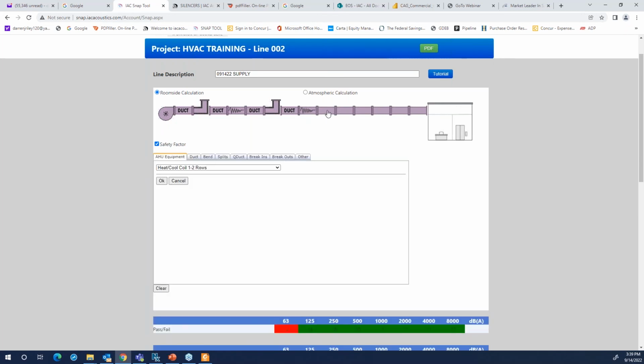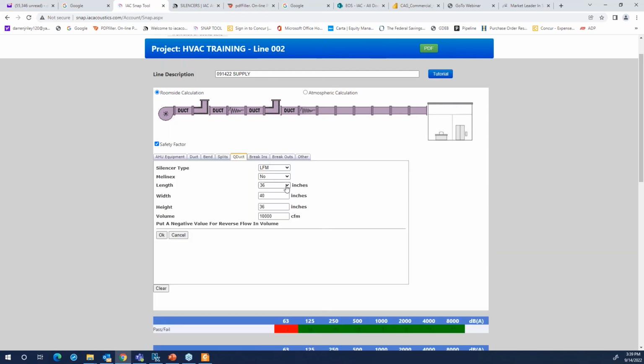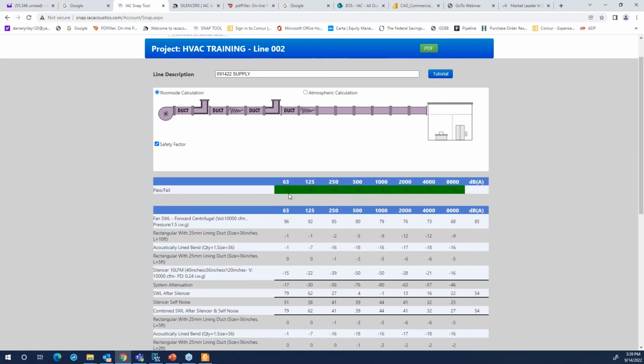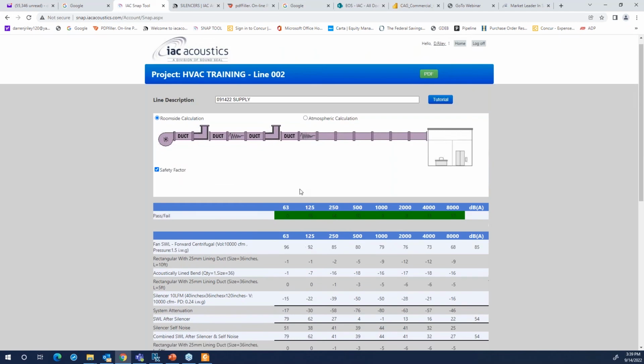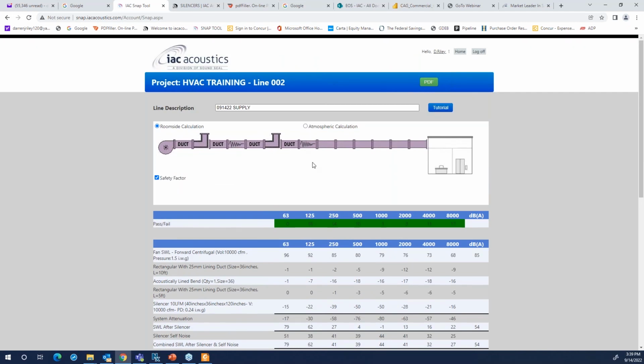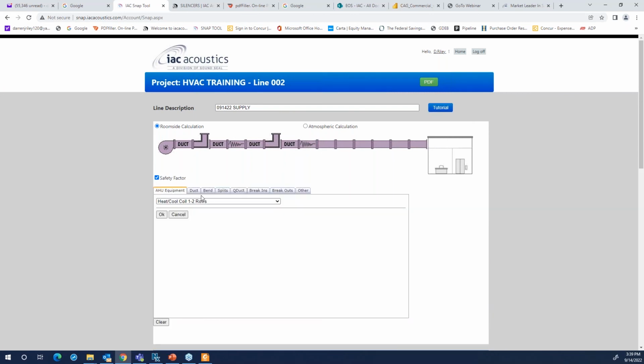So what I will do then is go in here and change this to 4 feet, see what happens. We're there, 0. No noise being put back in the system. Also, no loss. So this one wins. So what I can do is I have a 4 foot silencer and 2 feet of duct, so 6 feet. I need to close this off. So I can come back in here and put in duct here. I can put in 9 feet.